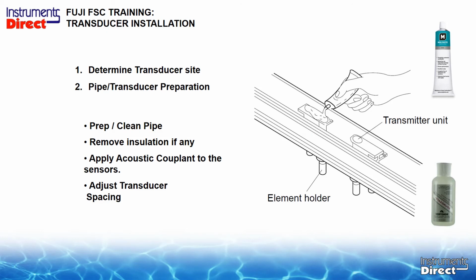And the biggest question I always get asked is how much acoustic couplant or sonic grease do we put on the transducer? And the simple answer is toothpaste on a toothbrush. The pipe is round, the transducer is flat. We just need an acoustic path to go from the transducer to the pipe itself. Grease comes in all different flavors. We prefer the silicone grease, but that's a whole video in itself.